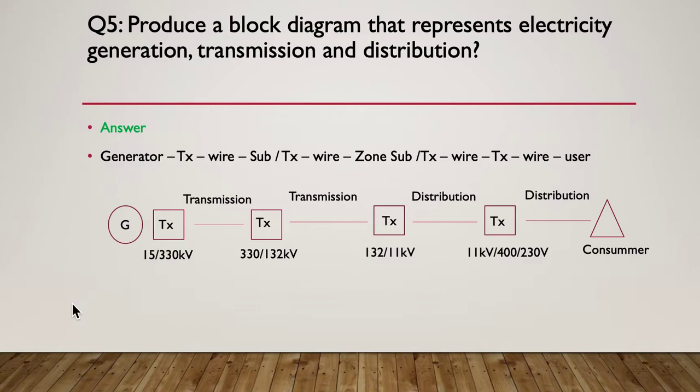So that turns into the diagram. It's just directly below here. So here's my generator. And I've got a transformer that steps the voltage up from 15 kV up to about 330 kV and that's called transmission. And then when we want to transmit shorter distances, we often drop our 330 kV down to 132 kV but it's still called transmission at that stage.